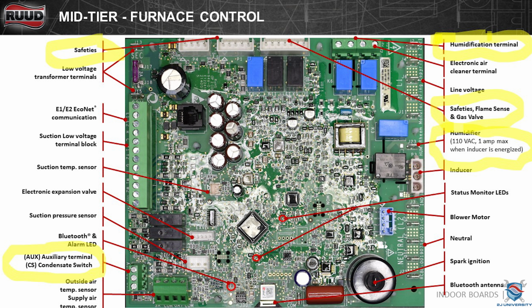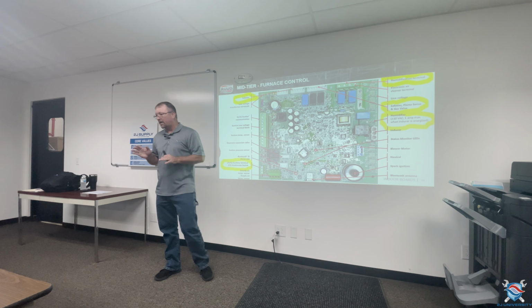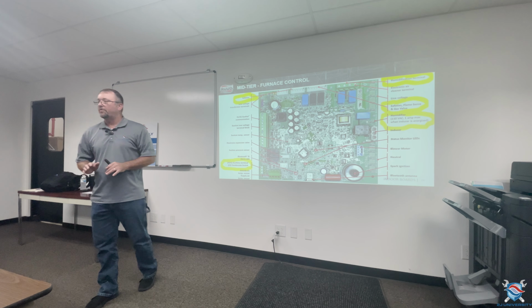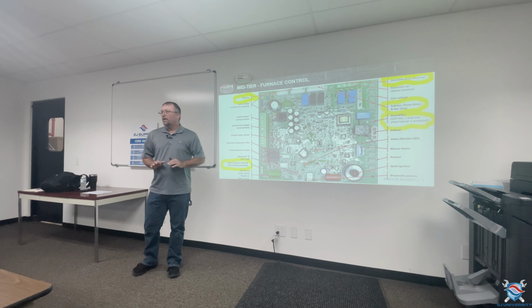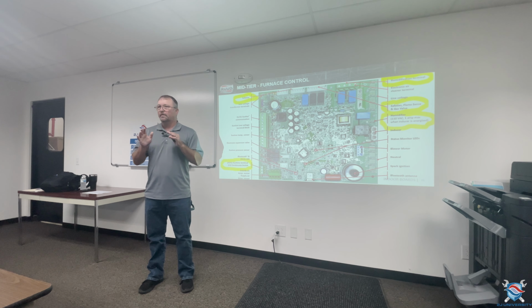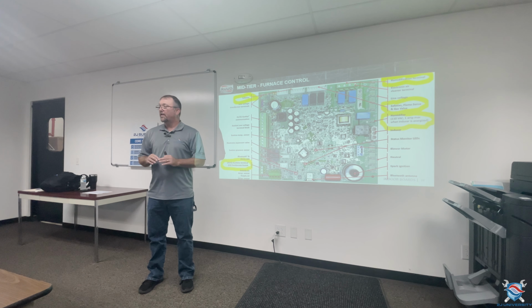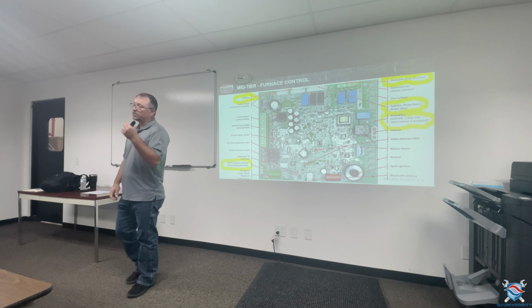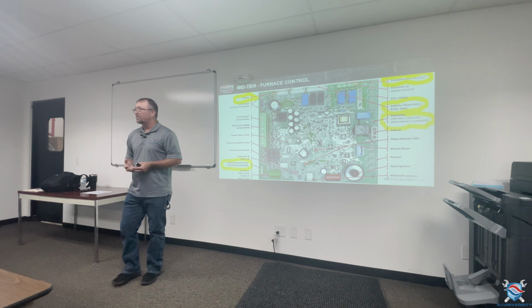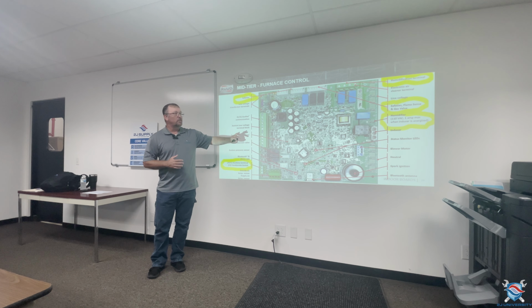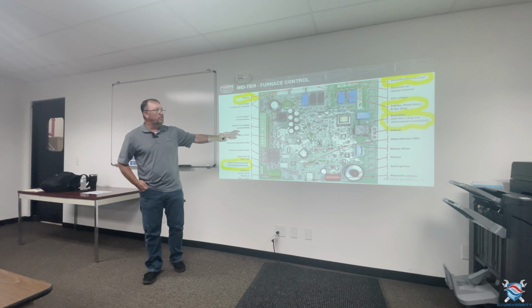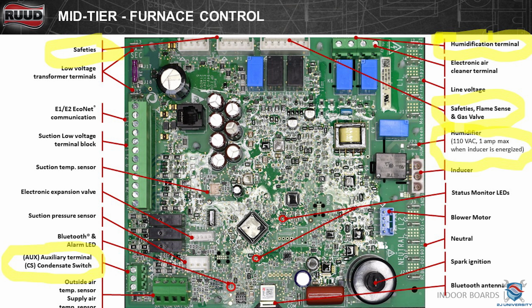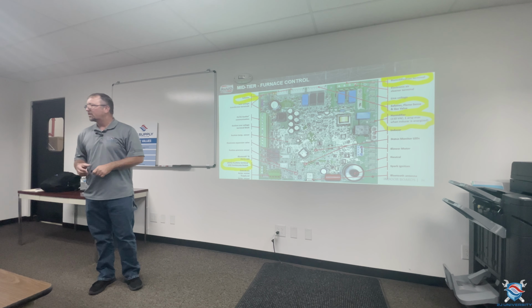One thing I want to talk about is humidifiers. I've worked with a lot of different manufacturers, and humidifiers are always that kind of thorn in my side. I always recommend measuring the humidifier terminals. There are manufacturers that use high voltage, there are manufacturers that use dry contacts, and some manufacturers will use both on the same board. So it's just one of those things I like to point out, because it is different depending on what board you have. Because if you look at this board, you not only have your 110 volt circuit on the board, but you also have a set of dry contacts. So depending on your configuration and how you want to configure it, it depends on which set you're going to use and how it's going to be energized.